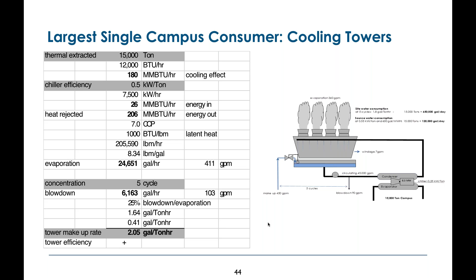I don't want to linger too much on this, but the cycles of concentration thing always kind of bugs me, how much water we've got to waste in order to evaporate. And I stuck the little formula in there to figure this out. Again, I used to think of 5 cycles of concentration as being a reasonable number. What that means is, let's say you've got 50 parts per million of silica in the incoming water, and you're trying to control your silica level in the chiller tubes in the recirculating flow to say 150 parts per million. Well, the cycles of concentration you need to achieve that is 150 divided by 50, or 3.